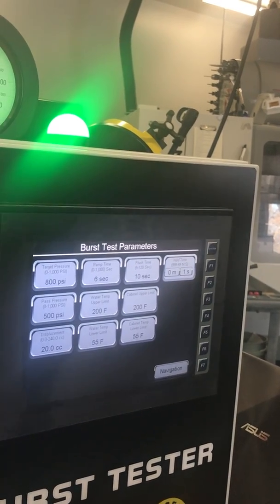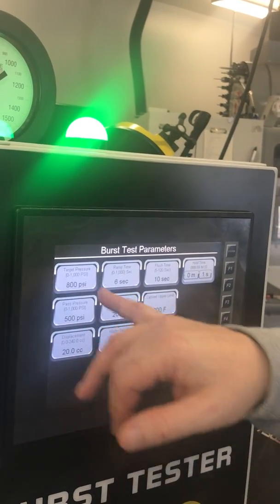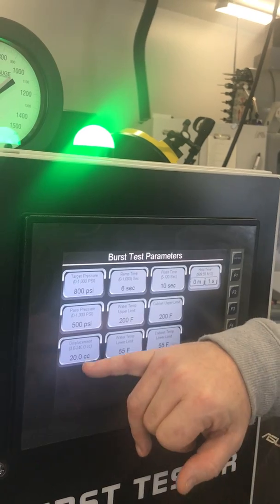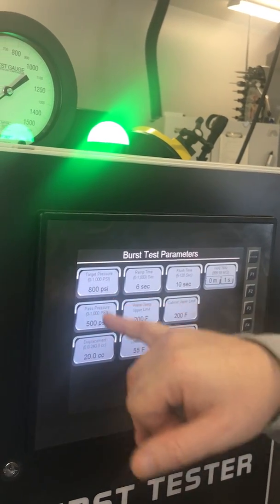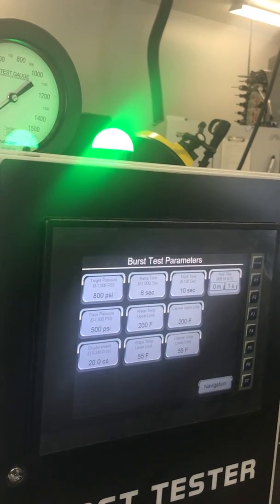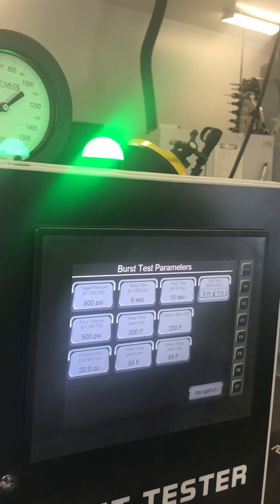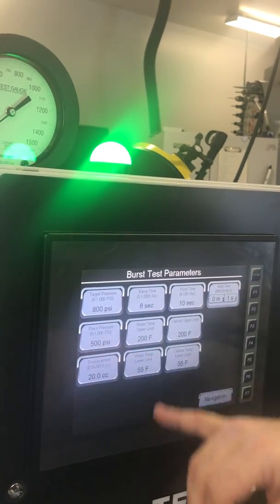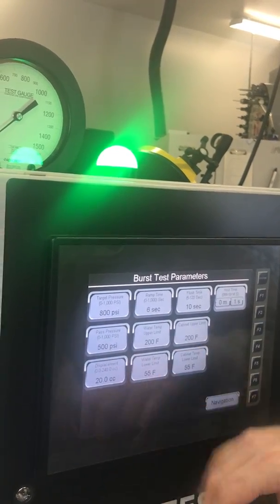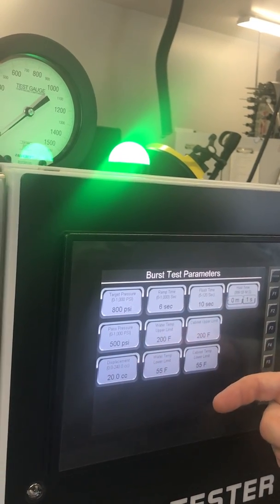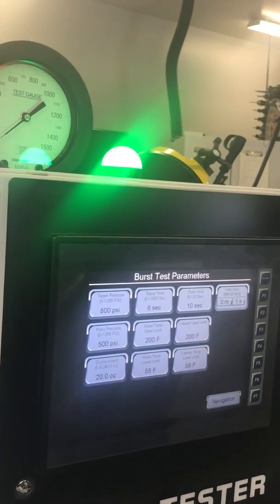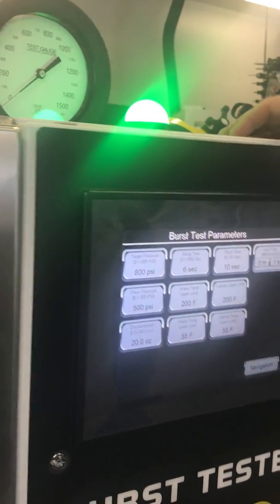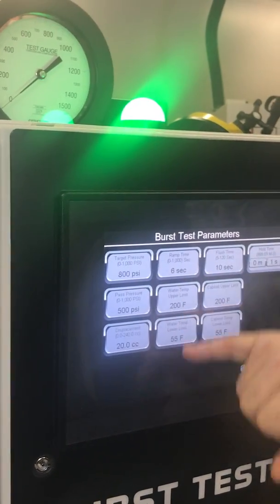The pass pressure, we're going up to 800 psi, but once you get to this pressure, or it exceeds that, it's going to pass the part. And you can adjust that 0 to 1,000. Water temperature limits. Just alarms? It's going to cycle stop. If you fall out of temperature right now, it's going to abort the test. And you get a low limit and a high limit.